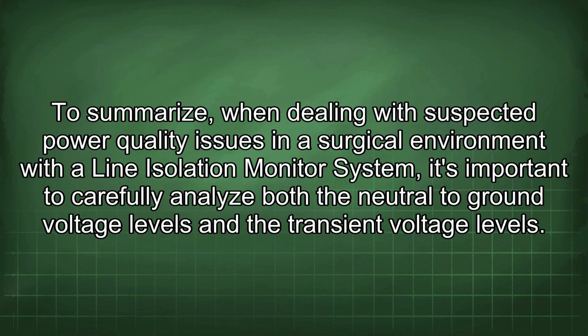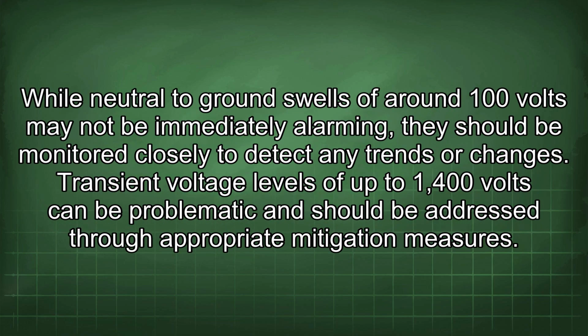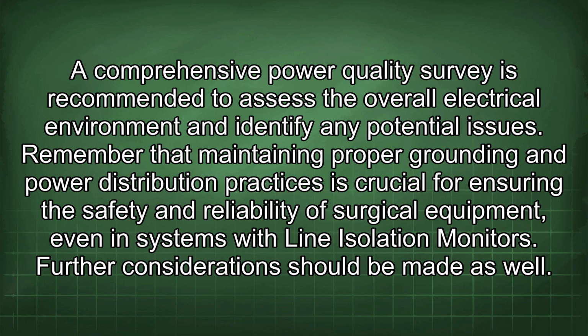To summarize, when dealing with suspected power quality issues in a surgical environment with a line isolation monitor system, it's important to carefully analyze both the neutral to ground voltage levels and the transient voltage levels. While neutral to ground swells of around 100 volts may not be immediately alarming, they should be monitored closely to detect any trends or changes. Transient voltage levels of up to 1400 volts can be problematic and should be addressed through appropriate mitigation measures. A comprehensive power quality survey is recommended to assess the overall electrical environment and identify any potential issues.